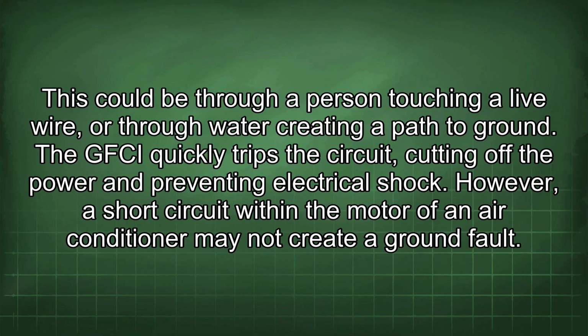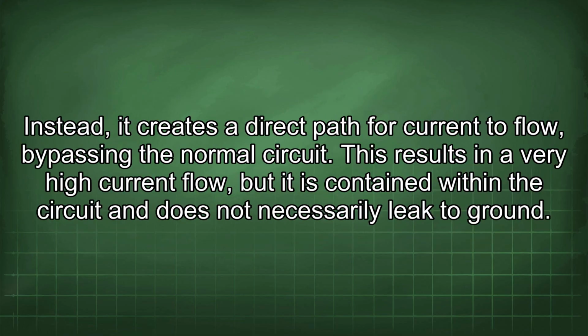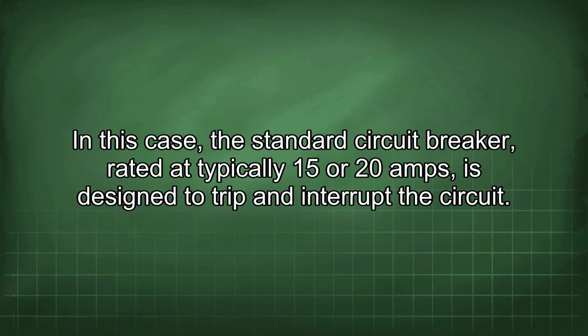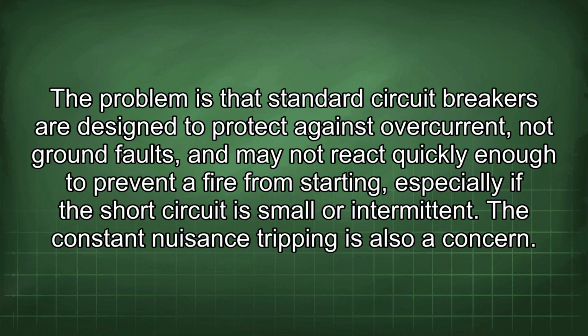However, a short circuit within the motor of an air conditioner may not create a ground fault. Instead, it creates a direct path for current to flow, bypassing the normal circuit. This results in a very high current flow, but it is contained within the circuit and does not necessarily leak to ground. In this case, the standard circuit breaker, rated at typically 15 or 20 amps, is designed to trip and interrupt the circuit. The problem is that standard circuit breakers are designed to protect against overcurrent, not ground faults, and may not react quickly enough to prevent a fire from starting, especially if the short circuit is small or intermittent. The constant nuisance tripping is also a concern.